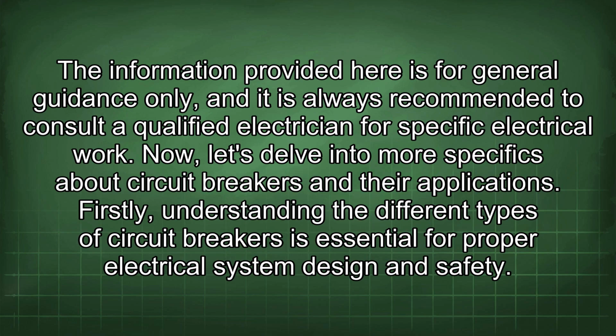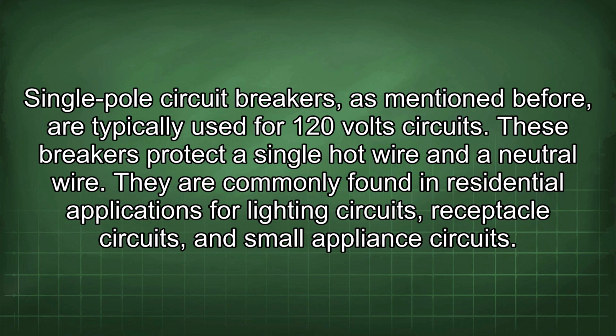Firstly, understanding the different types of circuit breakers is essential for proper electrical system design and safety. Single-pole circuit breakers, as mentioned before, are typically used for 120-volt circuits. These breakers protect a single hot wire and a neutral wire. They are commonly found in residential applications for lighting circuits, receptacle circuits, and small appliance circuits.